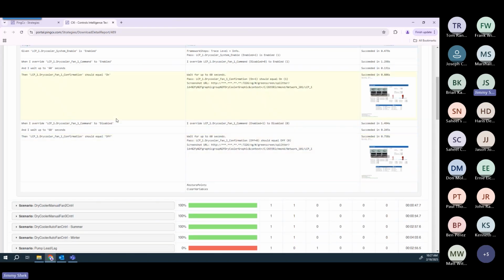Okay. And then lastly here, you'll see that after the tests are completed, you'll see this kind of restore points and clear variables tag listed on the trace. So as PingCx is going through these test scenarios, each test step, it's keeping track of any changes that it's making to the system, right? So whether it's a set point change or override, it's keeping track of all that, so that at the end of the scope, whether it's on a scenario level or on the feature level, it's putting things back to where it found it, right? So this way, it kind of eliminates that user error of someone keeping track of whatever set point values were before they made the change, right?